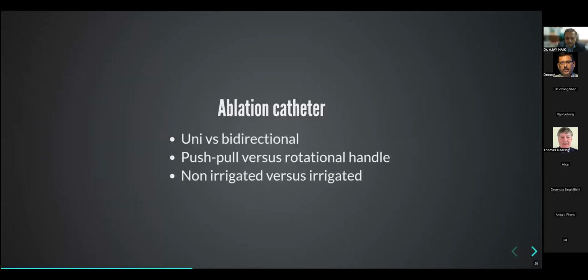And again, there are different types of handles and controls. You can use those. Irrigated catheters, ablation catheters, are always used on the left side because they reduce the risk of thromboembolism. Irrigated catheters are also used in situations where you need to produce a deeper lesion. They are also required if you are stuck in a place where there's poor perfusion, so the flowing blood is not cooling the tip of the catheter, and you keep getting temperature rise and inadequate power delivery. Then again you need an irrigated catheter.